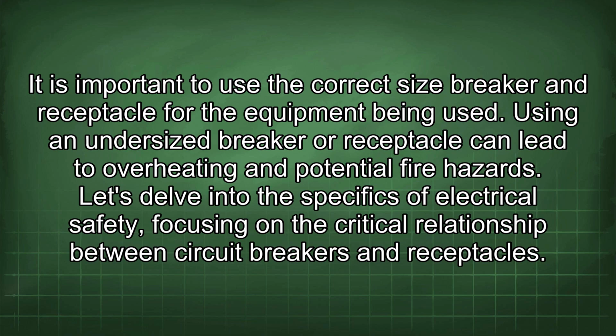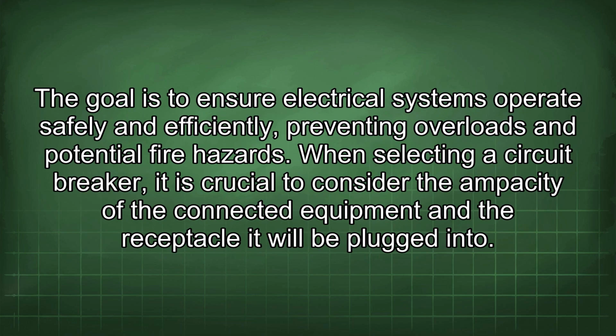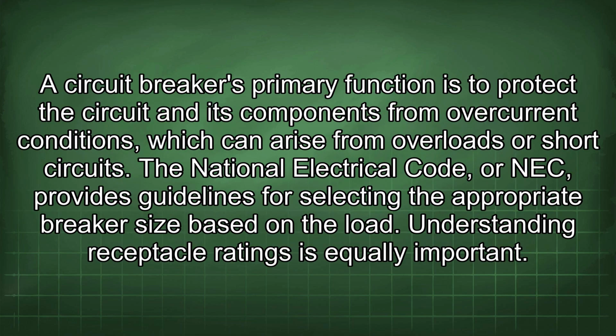Let's delve into the specifics of electrical safety, focusing on the critical relationship between circuit breakers and receptacles. The goal is to ensure electrical systems operate safely and efficiently, preventing overloads and potential fire hazards. When selecting a circuit breaker, it is crucial to consider the ampacity of the connected equipment and the receptacle it will be plugged into. A circuit breaker's primary function is to protect the circuit and its components from overcurrent conditions, which can arise from overloads or short circuits. The National Electrical Code, or NEC, provides guidelines for selecting the appropriate breaker size based on the load.